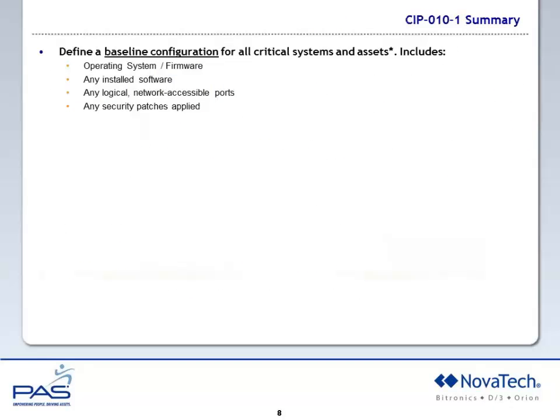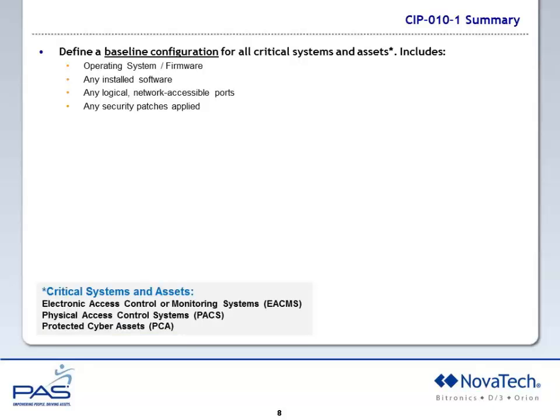Now for a summary of CIP 10. CIP 10 requires that you define a baseline configuration for all critical substation assets. This includes operating systems, firmware, any installed software, any logical network accessible ports, and any security patches applied. Critical systems and assets include electronic access control and monitoring systems, physical access control systems, and protected cyber assets.